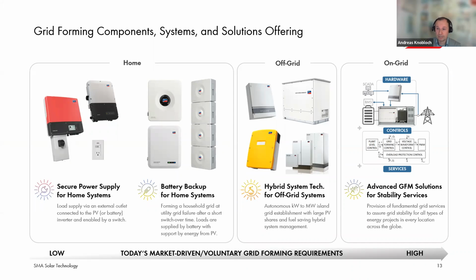Looking at SMA's offering of components, systems and solutions that we provide in a grid forming manner. On one side, we have grid forming capable components and systems for home customers. On the left side, you see applications that are provided by some of our PV inverters for home applications and also by our storage inverters for home applications. It's called a secure power supply for home systems. And this means that these systems, in case of a power outage, have an outlet, a socket where you can connect a load to and supply this load by PV power as long as the PV power is available. So as long as the sun is shining, and if the sun does not provide enough power, then of course you cannot supply the load that is connected to your outlet.